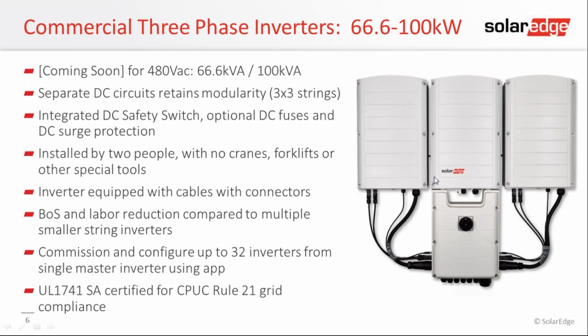With these inverters, we have local onboard Wi-Fi, and all an installer has to do is pull out his smartphone, connect to the inverter very simply, one touch of a button using the SolarEdge app, and then you can program and configure all of the inverters that are connected in a communication daisy chain. So using RS-485 Modbus, you can program all these inverters from one spot with your smartphone. So it's really easy to do, and I like it a lot.